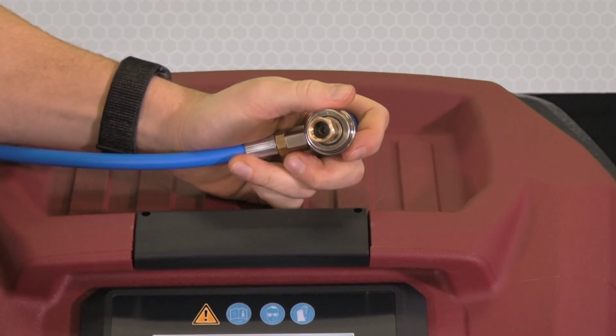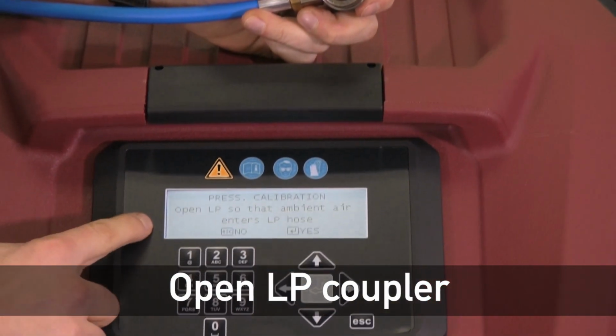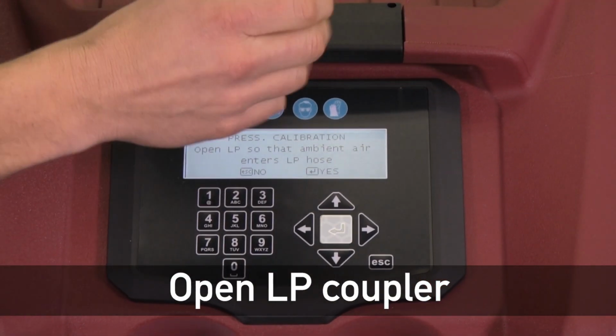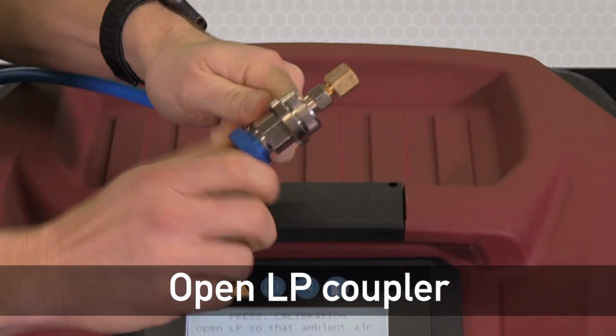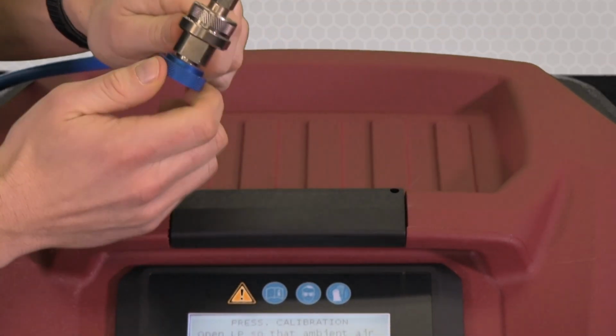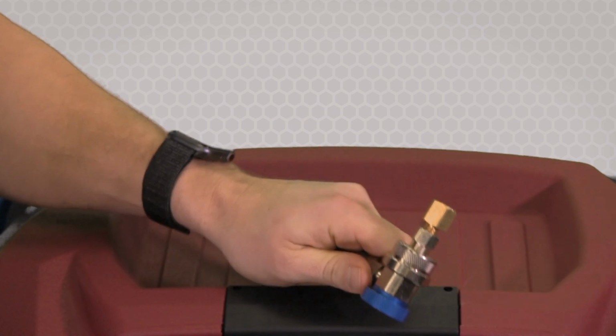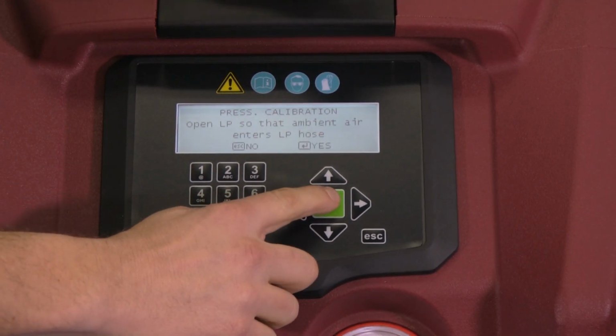In the next step, it says to open the LP so that ambient air enters the hose. So that's what we'll do. We'll open the coupler, and we should hear a little bit of a pressure release there. At that point, we can hit yes on the screen.